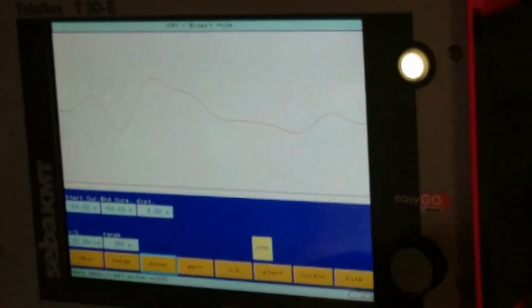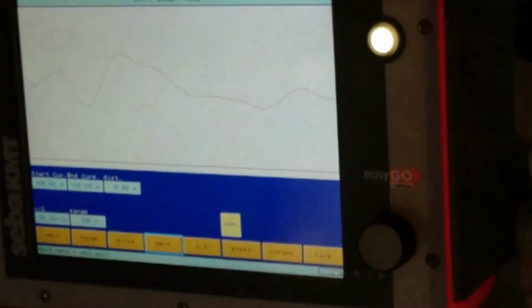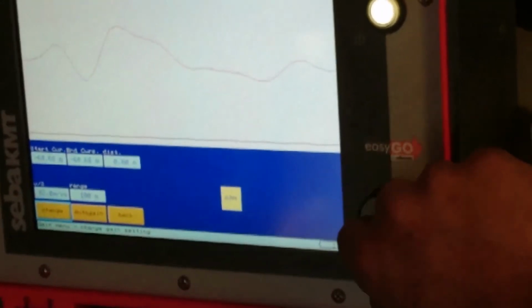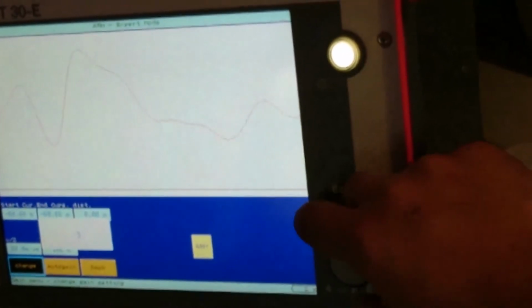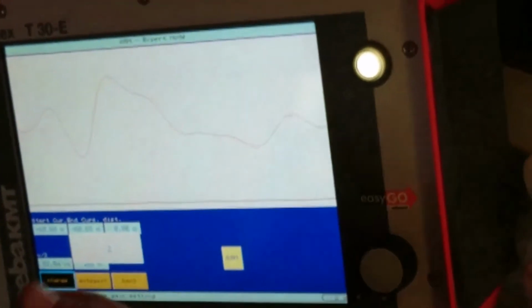Change the pulse width if the trace is not clear. You can change the pulse width and you can change the gain. If you go to the gain, you can change it, either use automatic or change it manually if it's not clear. See, if I change the gain, I can see a clearer picture, but if I change it too much, then I cannot see the top. So it's not good, I would like to see the top of the trace. This is a very good clear one, I can use it.